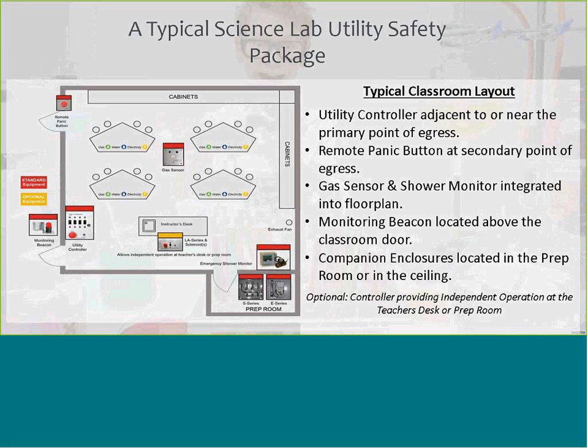One thing you don't want to do is have one control panel controlling multiple rooms. It's a safety issue: what happens if other rooms are unoccupied, and the instructor activates gas in their room, but other rooms have gas left open? It could start filling with gas and no one knows until hours later. So each classroom and prep room should have its own system, so you know when it's operated and what's actually being operated. Keep that in mind when designing your systems.